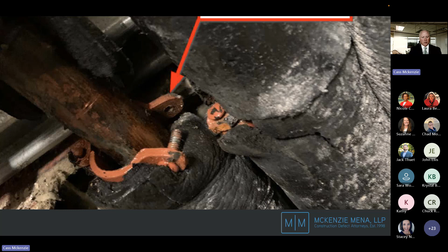The problem was they came up with their own support strut system—it wasn't designed or installed the way it was supposed to be. The weight of the pipe is now pulling the support away from the wall, it's separated, and the pipe is starting to sag. So first you'll have functionality problems with the system itself, but eventually you'll have failure of the pipe.